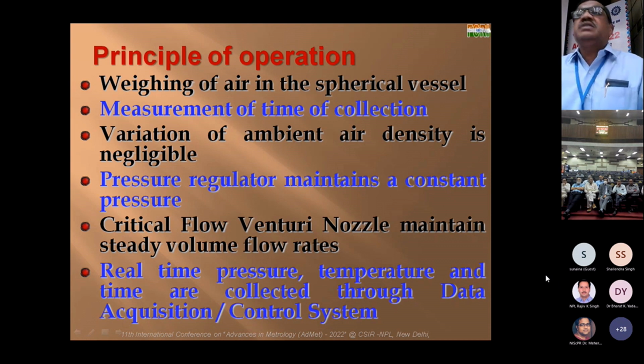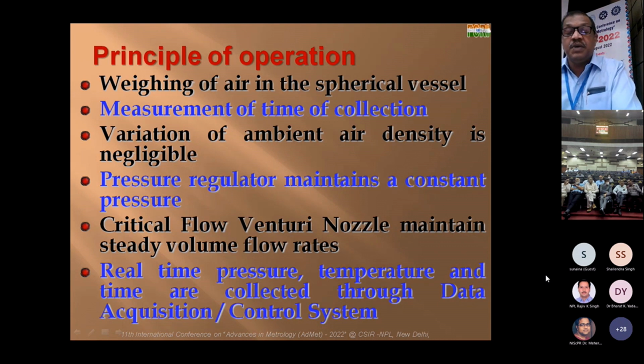Variation of ambient air density is negligible between the two mass measurements. So practically, buoyancy compensation we have not considered while making the mass measurement. The pressure regulator maintains a constant pressure. It can maintain the downstream pressure to better than 1% of the upstream pressure. With the critical flow venturi nozzles, we maintain the flow rate, and real-time pressure, temperature, and time are collected through the data acquisition system.